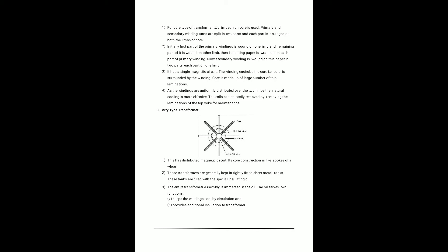The berry type transformer has a core with HV windings, insulation, and LV windings. It has a distributed magnetic circuit with a core construction like the spokes of a wheel. These transformers are kept in a tight-fitted metal tank filled with special insulating oil. The entire transformer assembly is immersed in oil, which serves two functions: keeping the winding cool by circulation and providing additional insulation.